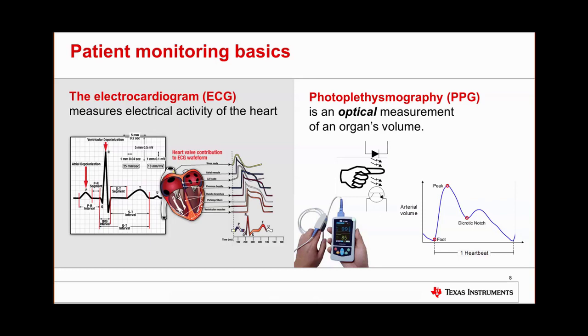Pulse oximeters use two specific wavelengths of light: red at 660 nanometers and infrared at 940 nanometers. The absorption at each wavelength allows physicians to isolate light absorbed by arterial blood from venous blood and other tissues. This is primarily used as an indicator of oxygen concentration in the patient's bloodstream. When measured simultaneously with ECG, both waveforms can be overlaid — they will have the same period, allowing heart rate determination. The time difference between the ECG peak and the PPG peak is called pulse transit time, which can be used to calculate systolic blood pressure and other parameters.